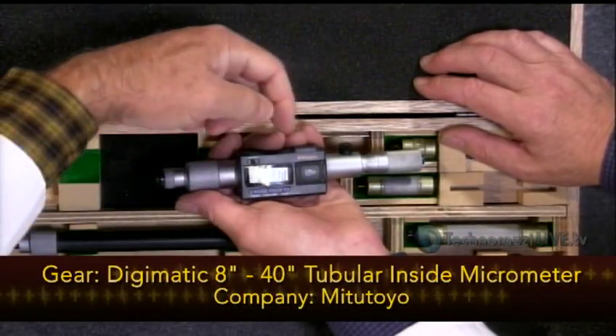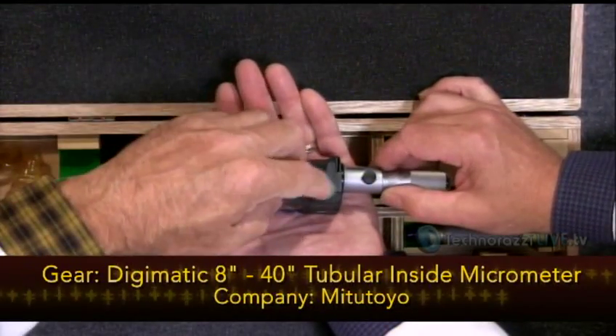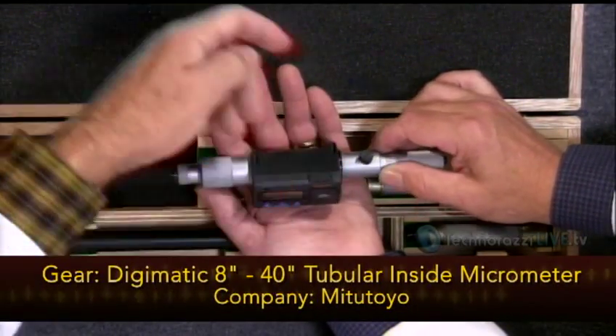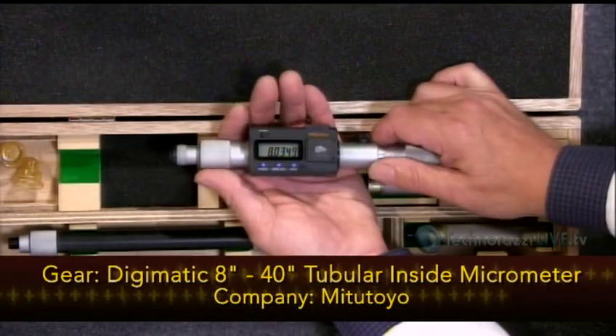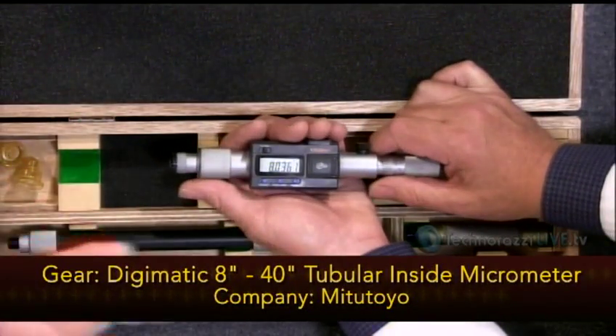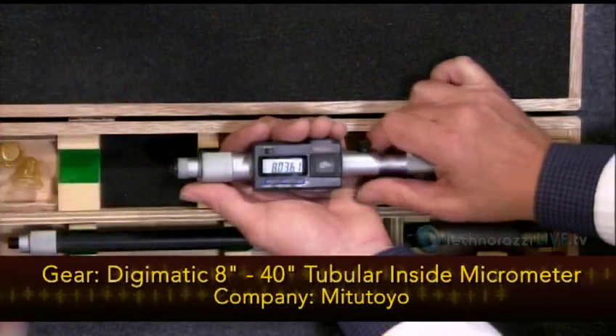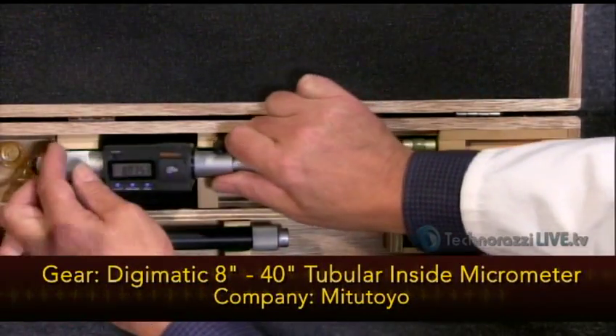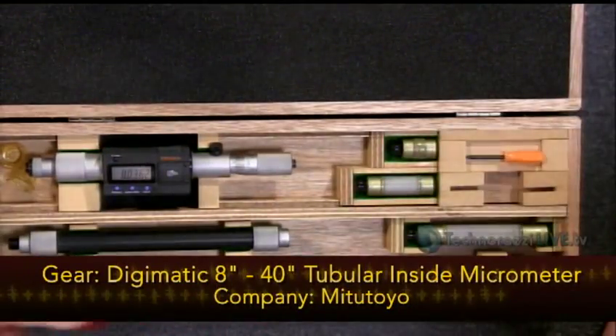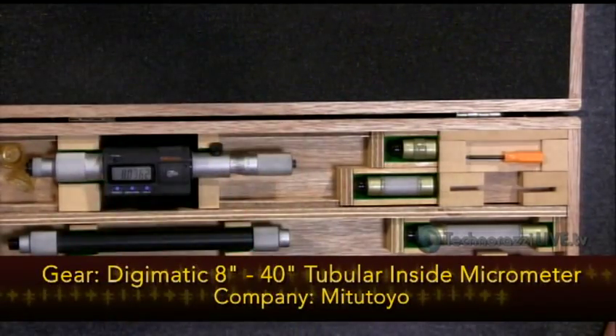Also, I should mention this one has what they call a Digimatic output, a digital output. Most modern electronic gauges do have a digital output, and one of the real advantages of that, aside from being easy to read, is if you're using some sort of gauge calibration software, such as PQ Systems GAGEpack, or any other calibration software.